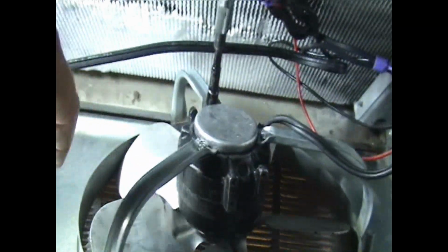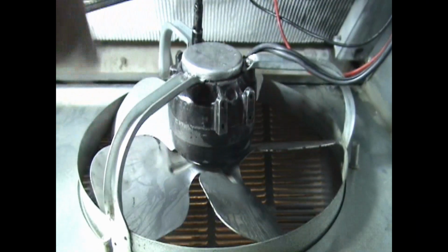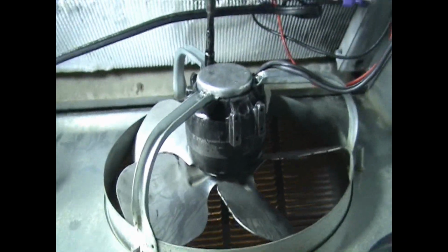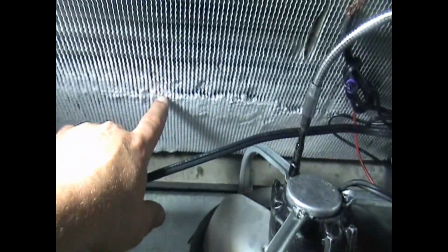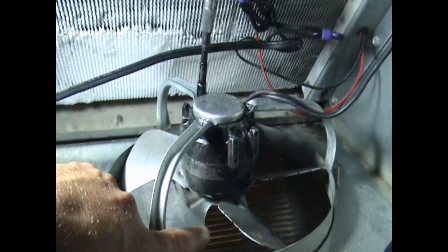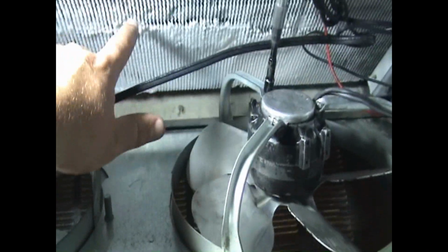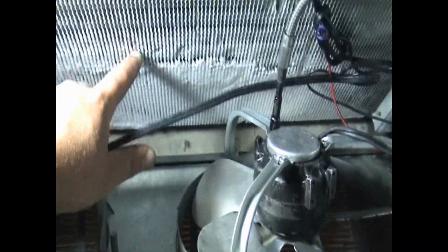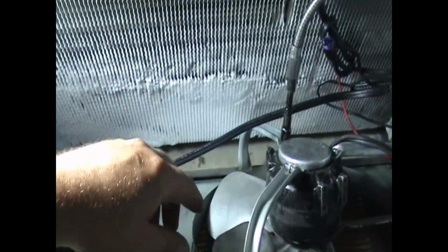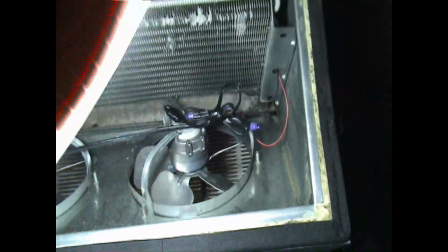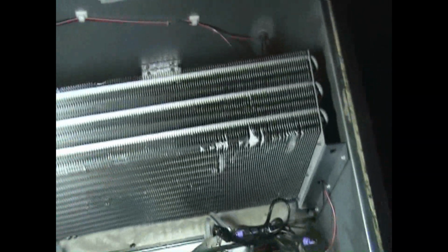So let's take these three brackets off, drop the fan motor out, switch the fan blade around, wire that guy back up. There's a little bit of frost over here from the fan going too slow, so I'll get all that off - it's not very much on there - and I'll double check with the frost timer on this and reset it. Okay, we got the new fan motor in there. I got rid of that ice.